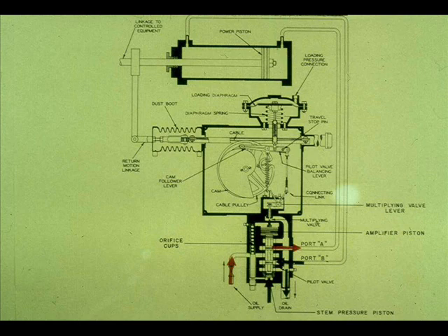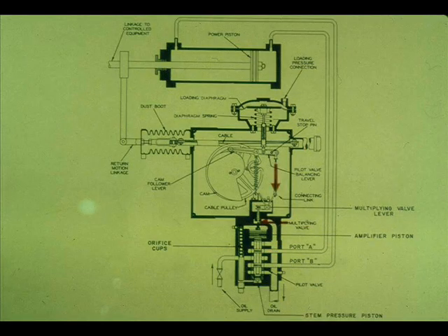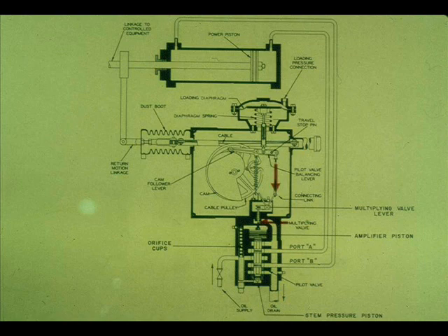Now let's see what happens upon an increase in the instrument signal. The connecting link lowers. This opens the multiplying valve. The amplifier piston is forced up. Port A is connected to supply. Port B is connected to drain.